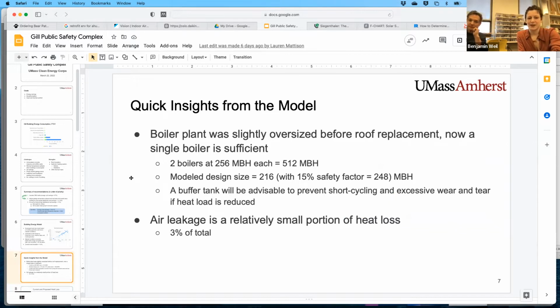So some quick insights that we got from the model is that the boiler plant was slightly oversized before roof replacement, and now a single boiler is sufficient. And a buffer tank will be advisable to prevent short cycling and excessive wear and tear if the heat load is reduced. So essentially the size of the boiler plant is determined by the rate at which it needs to supply heat in order to meet heating loads. And once you insulate more, you reduce the rate of heat loss, which leads to a lower heating load, which means the boiler can be smaller. And if it's oversized, you can have issues with short cycling, which, like I mentioned, can cause excessive wear and tear.